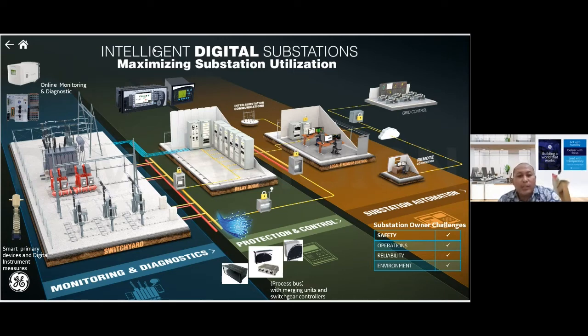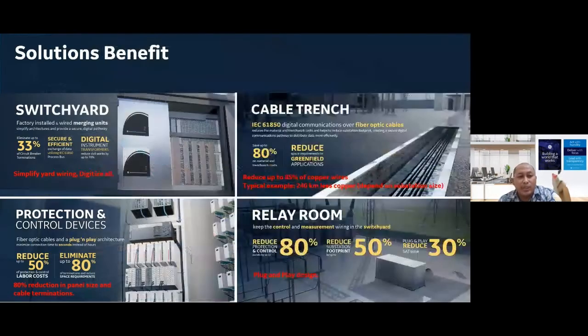So here we go to the next slide. This is related to the solution benefits of the digital substation. On the switchyard side, by having this digital substation, it can eliminate up to 33% of circuit breaker termination. And it is more secure and efficient in exchanging data by utilizing the 61850 protocol process bus. In terms of the digital instrument transformer, it can reduce civil work by up to 70%. On the side of the cable trenches, it can save up to 80% on material and trenches work, and it can also reduce the requirement of greenfield applications.